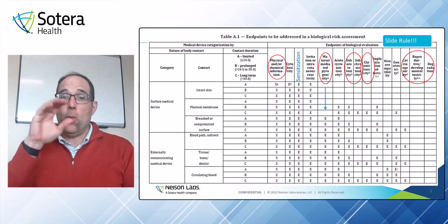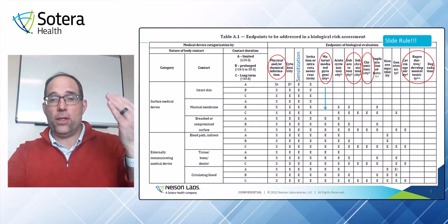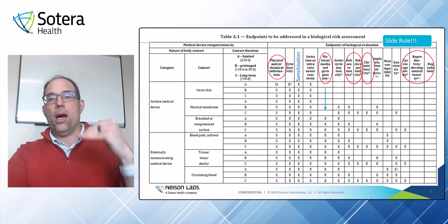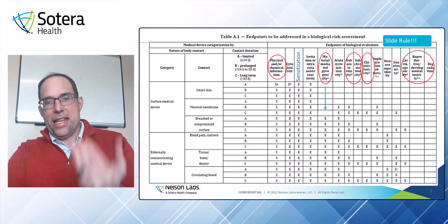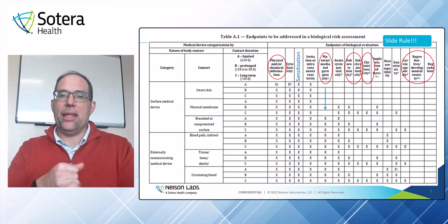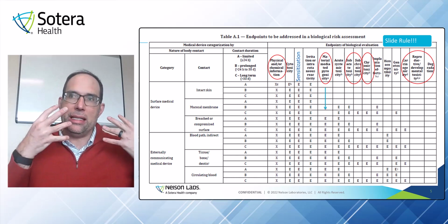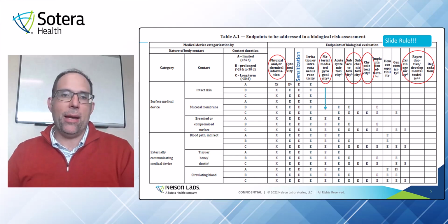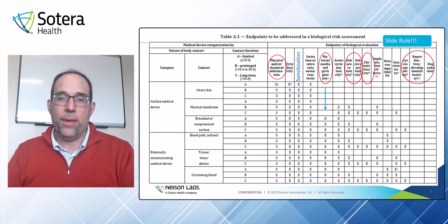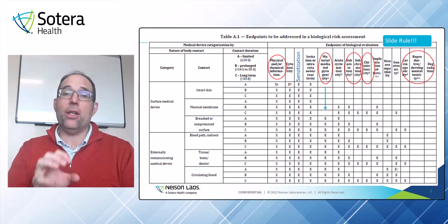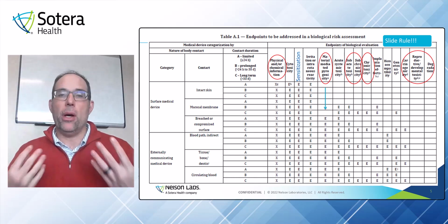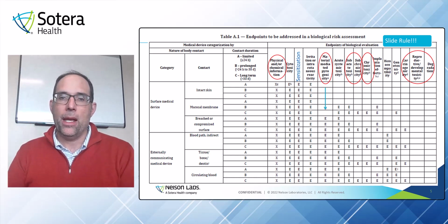And as you can see, the first column we added here was physical and/or chemical information. So the concept here is before you do anything with your device, you need to understand the type of information, or what is going in it materials-wise. So what kind of physical or chemical information do you have on the materials and processing of your device? That's required. So you have to do some kind of research, understanding, testing, or something to help you understand the physical or chemical information.